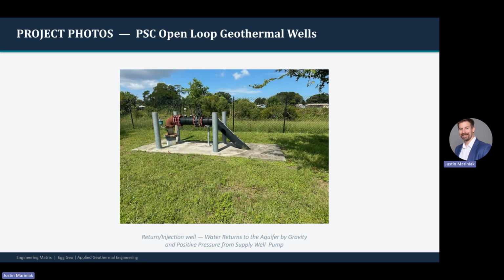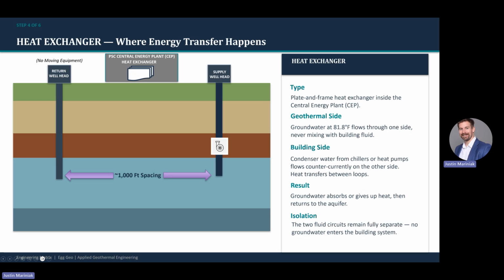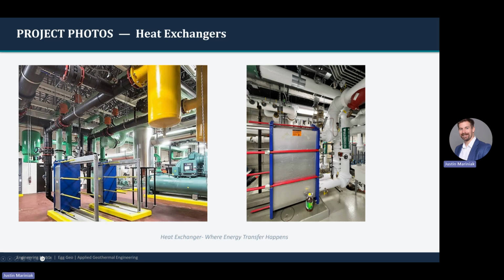This is one of the return wells. Notice there are valves and gauges, but no electrical disconnect. Between the two wells is a central energy plant, which houses the chillers and heat exchanger. The heat exchangers are plate and frame type. They are composed of stainless steel plates that have channels between, allowing two different water streams to transfer heat without touching. This is where the building heat is transferred to the groundwater. Here are some photos of heat exchangers in a central energy plant. Notice how little space they take up, especially compared to that of a cooling tower.